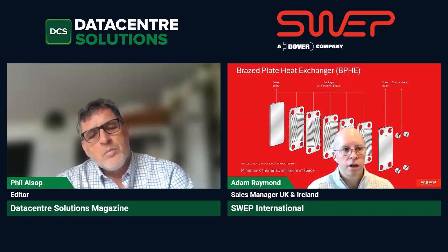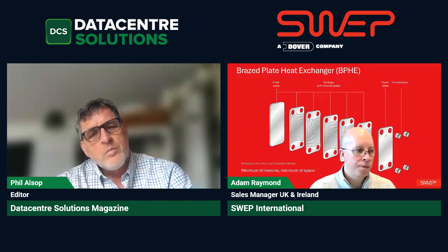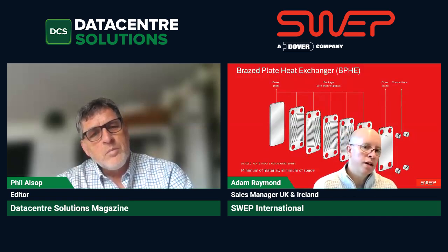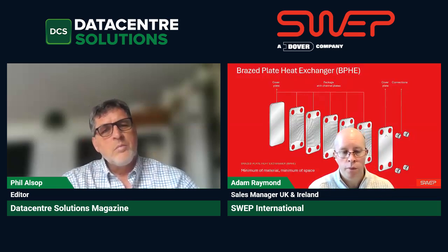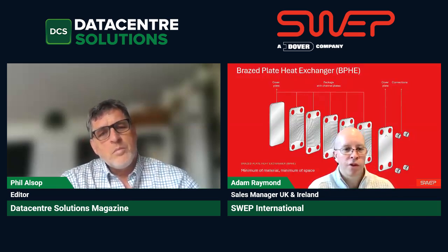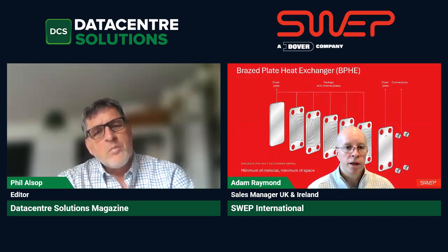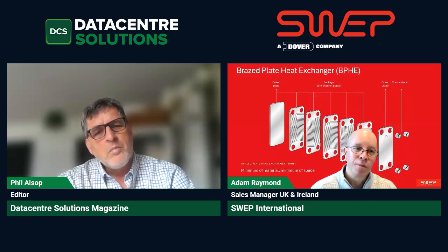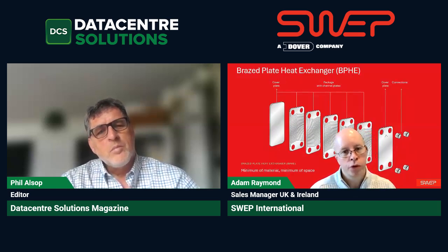Then we get things like the immersion cooling guys who are concerned about the fluid in their dielectric tank or two-phase immersion, which is non-conductive. If we've got water on the other side - plain water - and the heat exchanger fails, we've got mixing of the two fluids and we're going to ruin quite an expensive lot of equipment. Fortunately we have products that mitigate that already, but then we've got the chemical compatibility of these different fluids being used, different product sizes - something as small as that - because they have existing server cabinets that they need to fit everything into. And then even down to other small details like the type of connections that they use. Some of these are not so familiar to us in our more traditional industries.